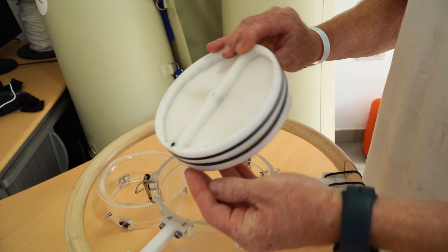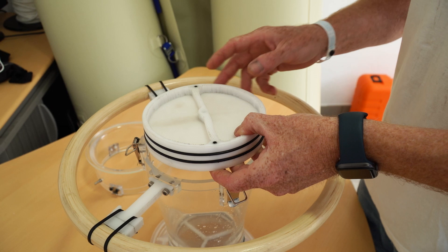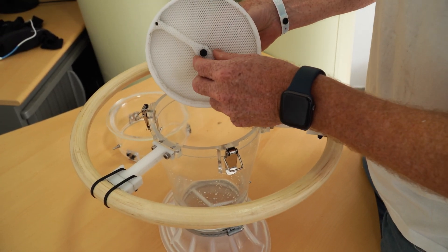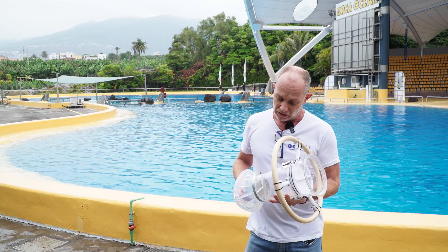In the middle is what really helps us analyze the difference in pressure — a capillary filter, basically a filter with many tubes. What you do is create a laminar flow with a pressure differential, and from there you can obtain volumetric flow rates. Then we have a lower port for gas analysis.